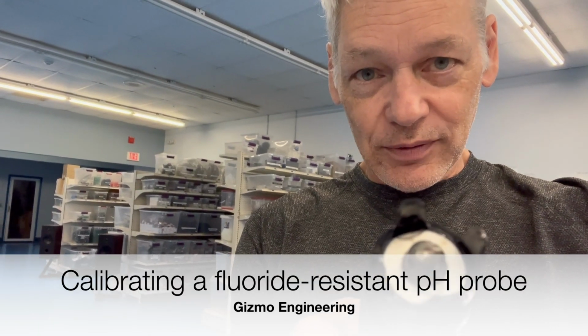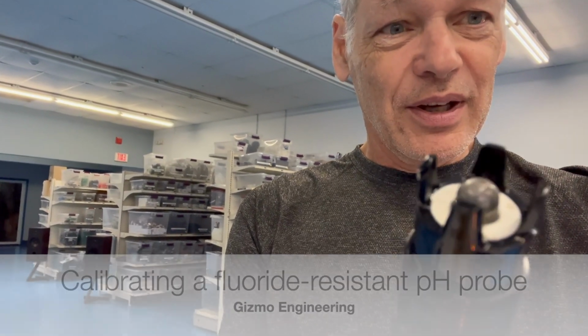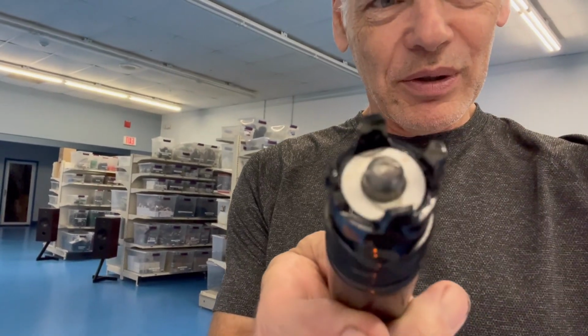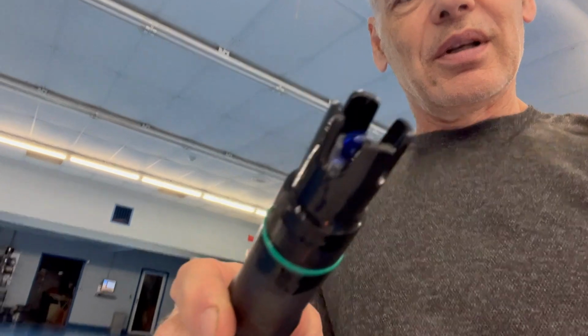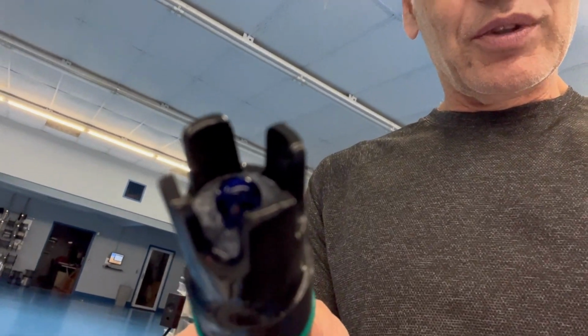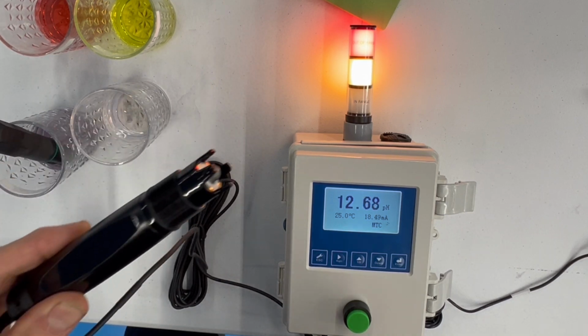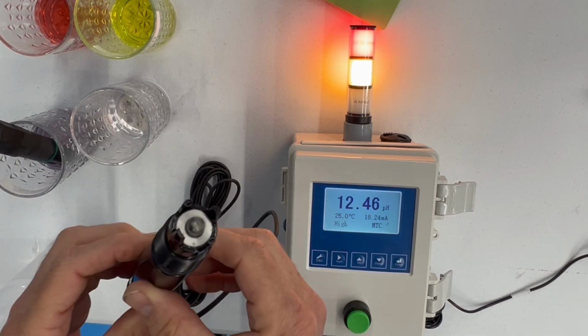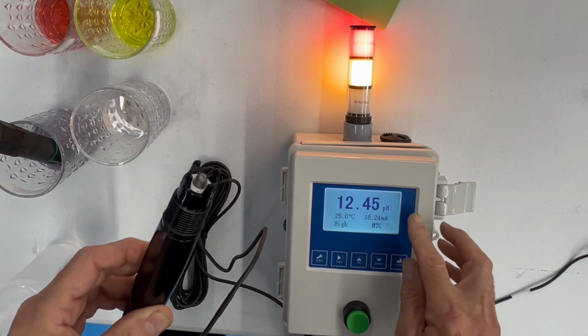Today we're going to be looking at the fluoride pH probe. Notice that it's got a metal bulb instead of the typical glass bulb that we see on our standard pH controllers. So here we have the antimony pH probe connected, and you can see the reading is 12.46.